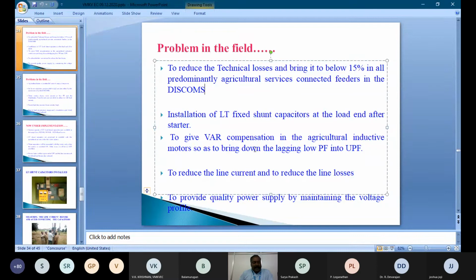maintaining the voltage profile. Normally, from the distribution transformer, the voltage is 230 volts in single phase and 433 volts in three phase. The distribution line runs about 1 or 2 kilometers on the LT side. And at the tail end, the consumer may suffer a low voltage problem. The consumer may get 180 or 190 volts or so, and in three phase about 350 or so. So he faces problems running the motors. But if shunt capacitors are provided, the voltage profile will increase sufficiently.